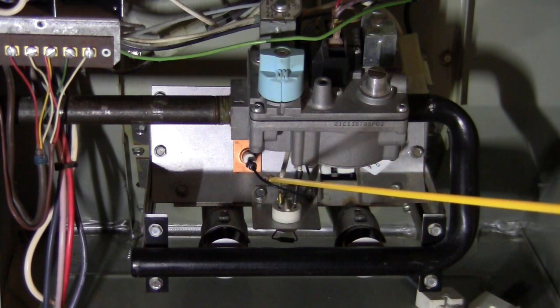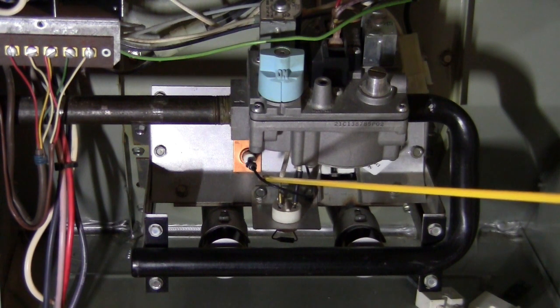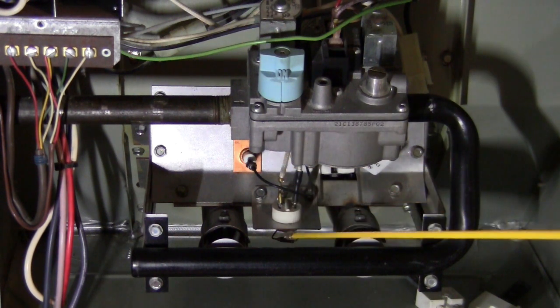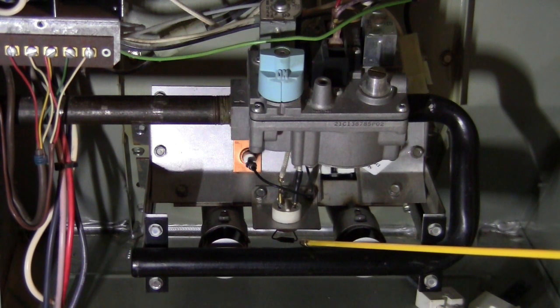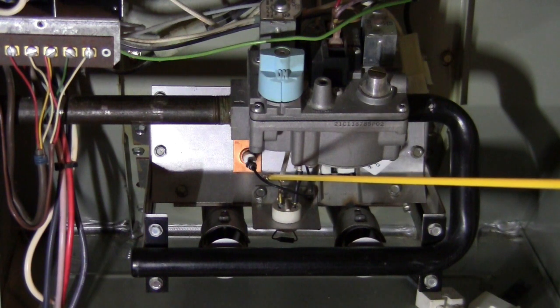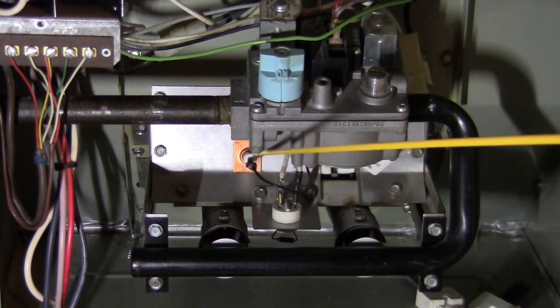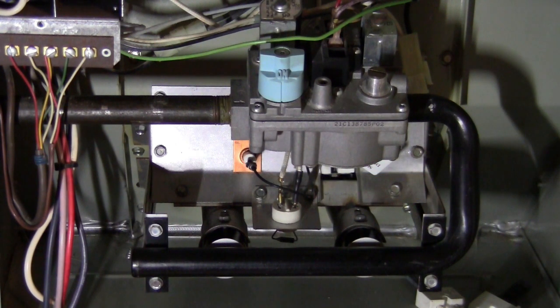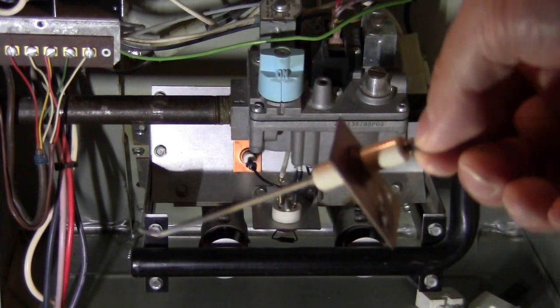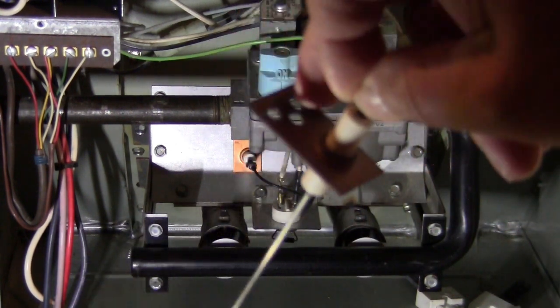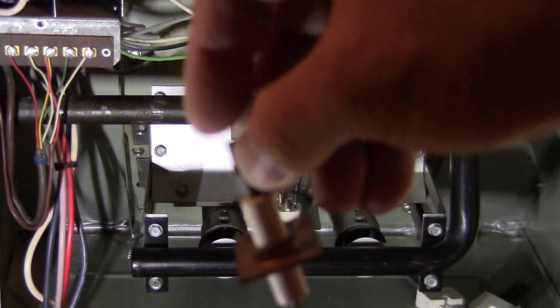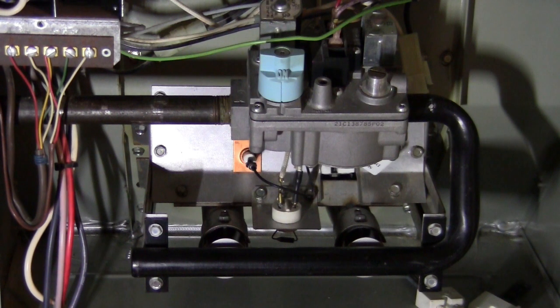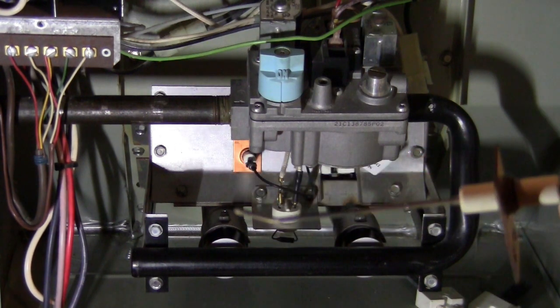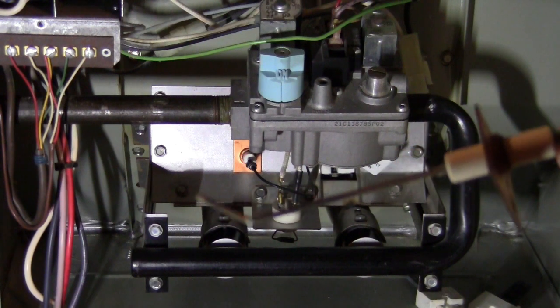And I watched a video by a professional who did service for many years. He rated the 10 most common problems in the furnace, and this one is the first. This is the first thing that causes the furnace to stop working. And basically, replacing it is very simple. Just one screw over here and one connection from here. Anybody can do that. But in the majority of cases, the sensor is not broken. It just got dirty. Something built up on the surface.